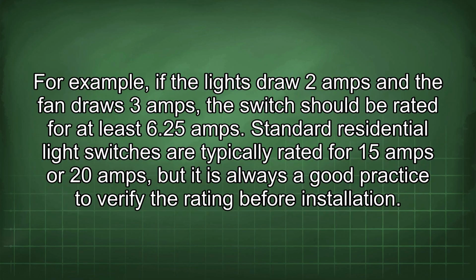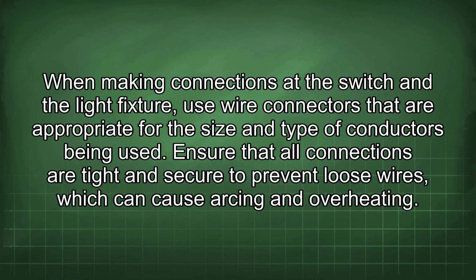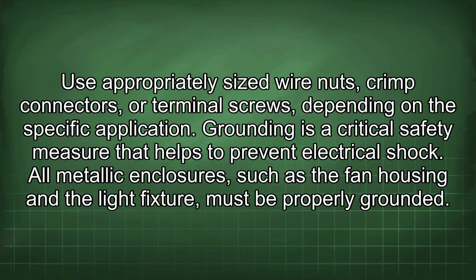For example, if the lights draw 2 amps and the fan draws 3 amps, the switch should be rated for at least 6.25 amps. Standard residential light switches are typically rated for 15 amps or 20 amps, but it is always a good practice to verify the rating before installation. When making connections at the switch and the light fixture, use wire connectors that are appropriate for the size and type of conductors being used. Ensure that all connections are tight and secure to prevent loose wires, which can cause arcing and overheating. Use appropriately sized wire nuts, crimp connectors, or terminal screws, depending on the specific application.